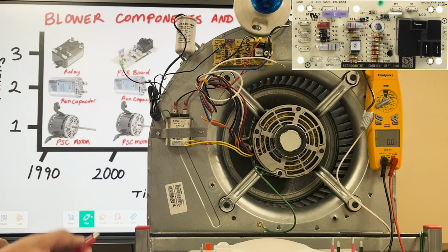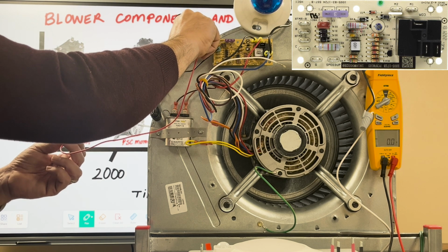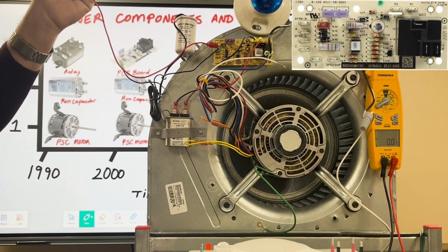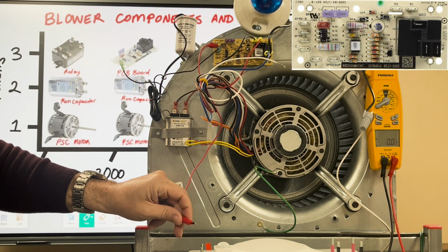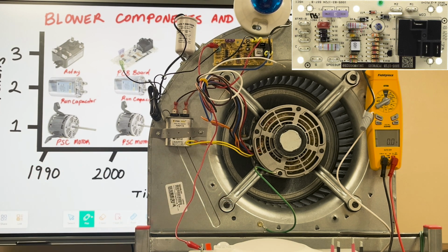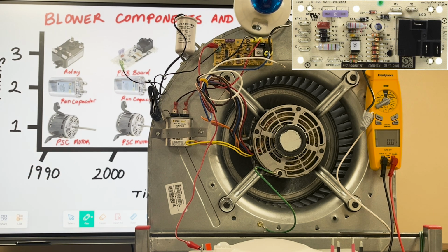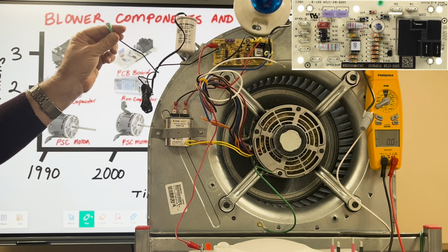I'm going to take 24 volt primary and run that to R down on my transformer. So we have 24 volts going into the board, and coming out of the board we're already coming across the float switch, so right now we would have 24 volts right here.